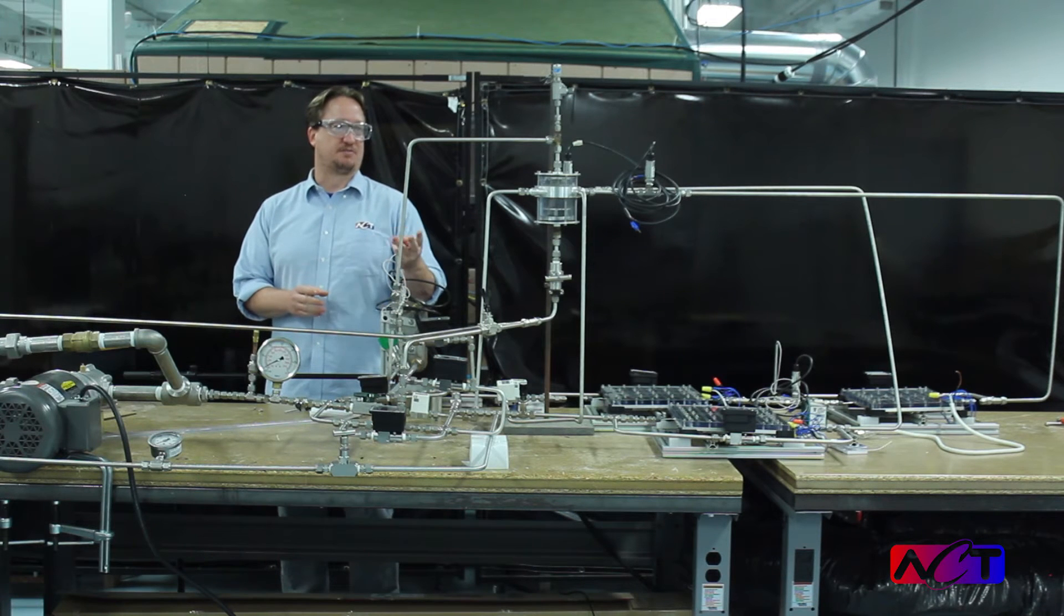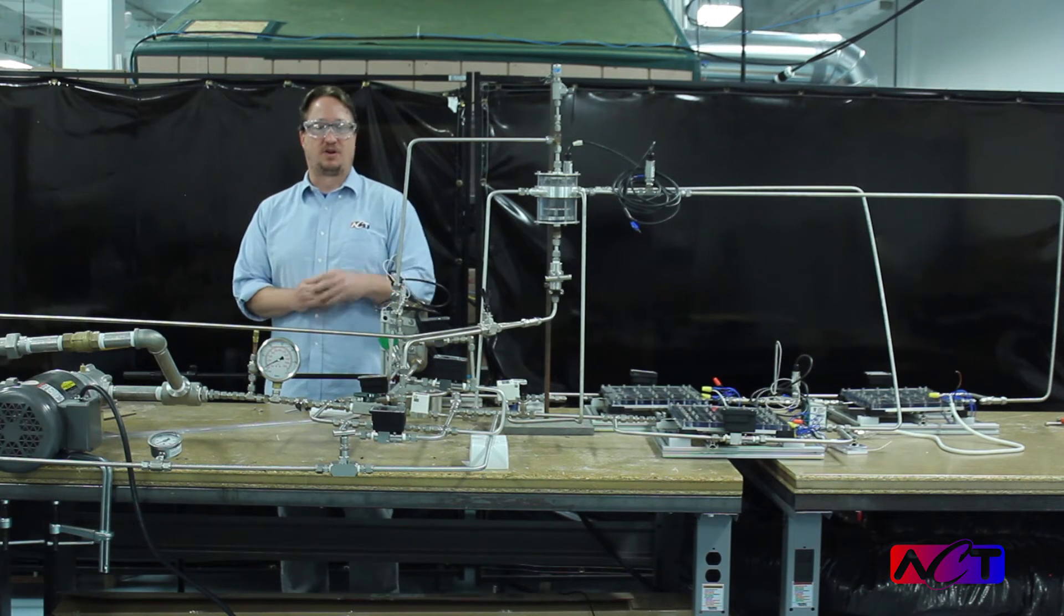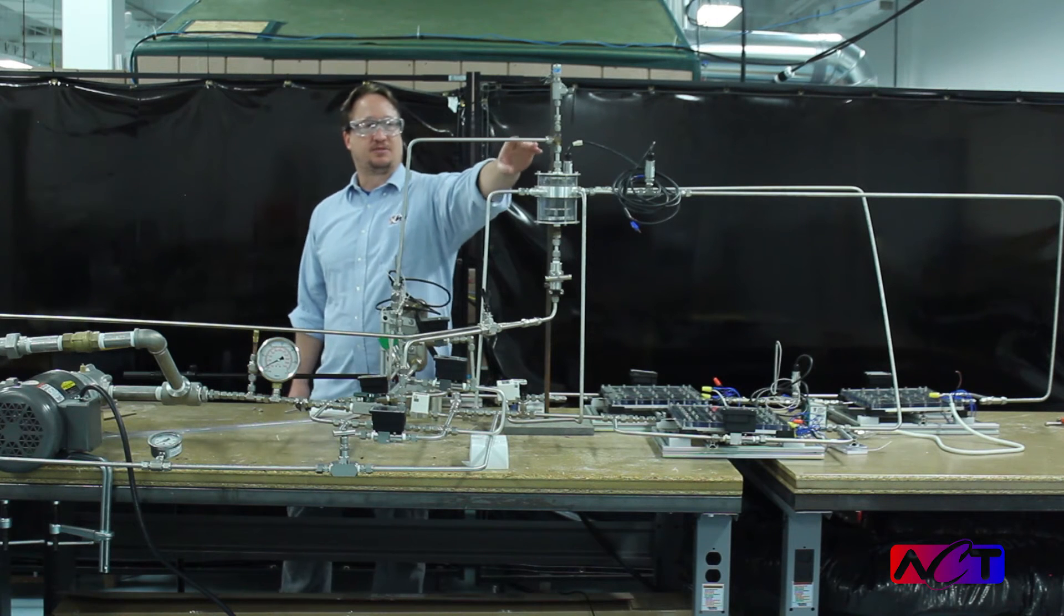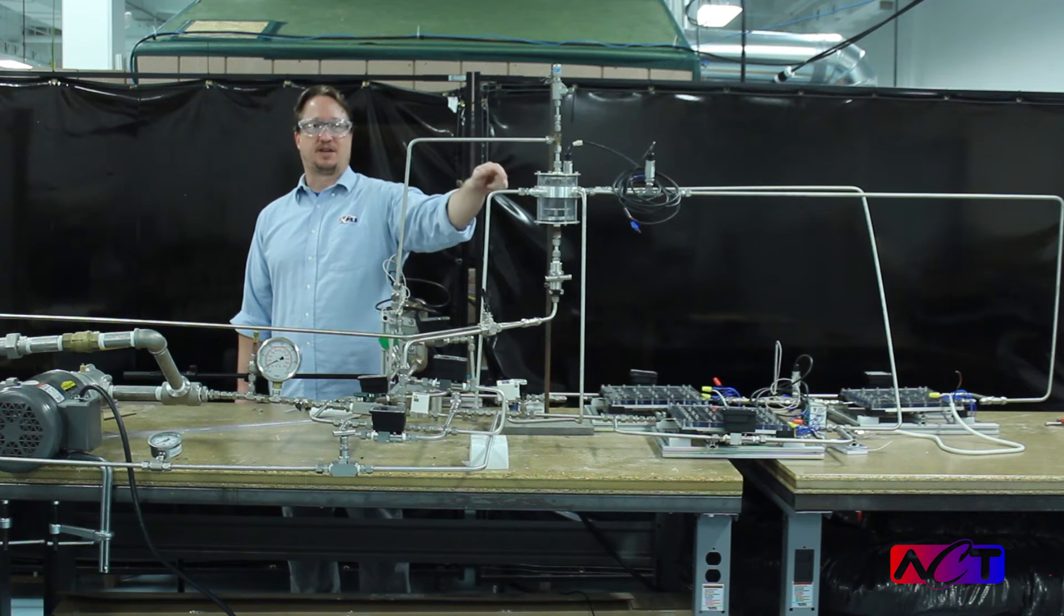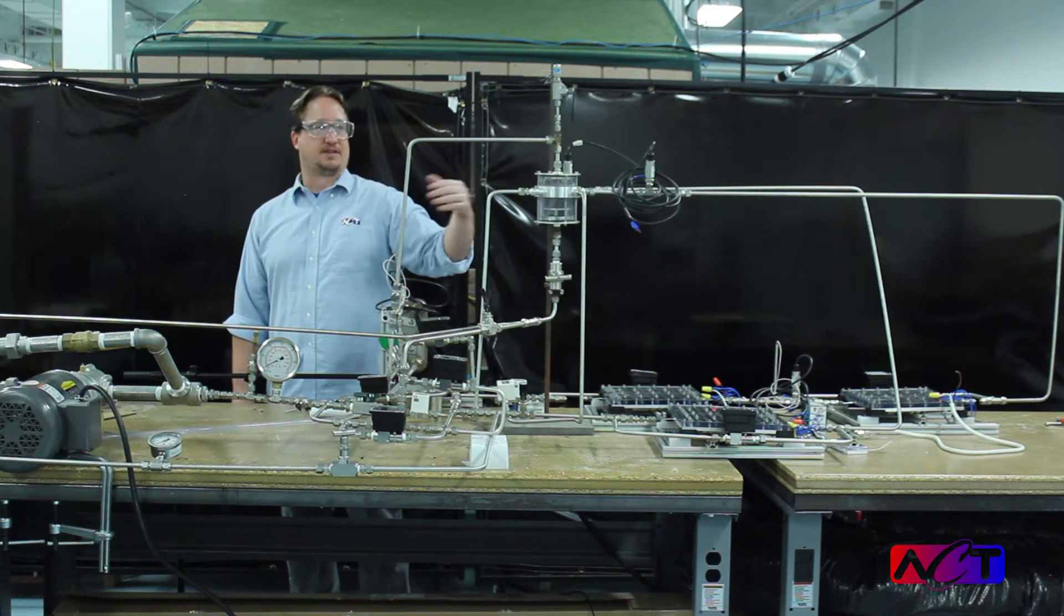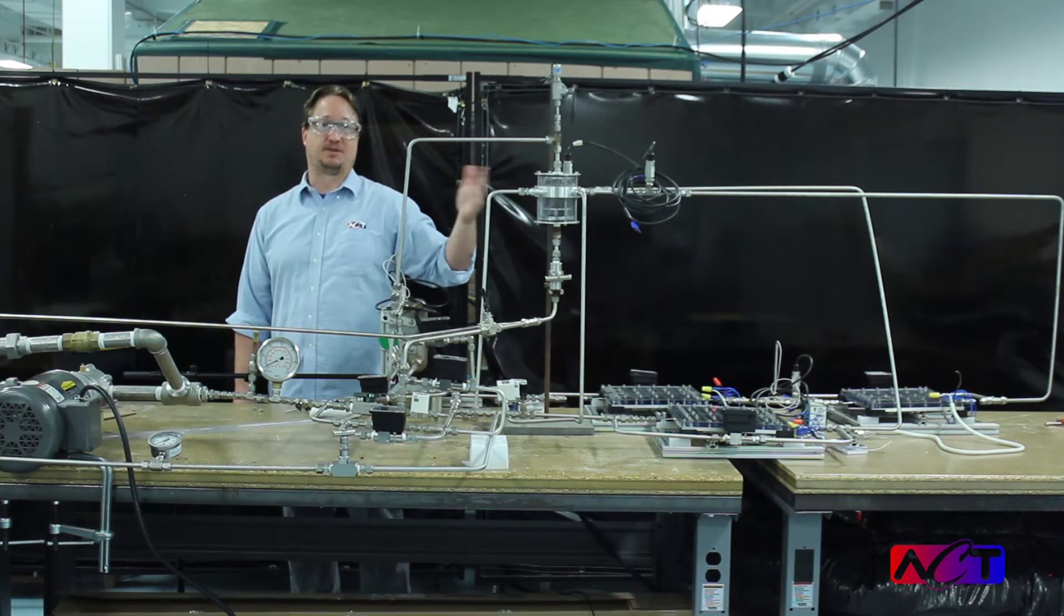There's three major components to this system. One of them is the phase separator. The phase separator that we use is a cyclone style separator and its job is to separate vapor and liquid that return from the evaporators or even maybe from the condenser, so that way the evaporators don't have to completely evaporate all the working fluid.